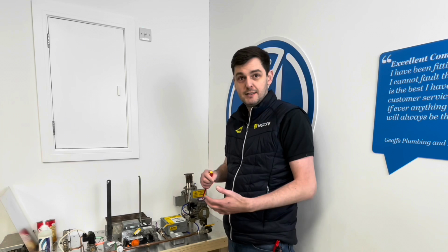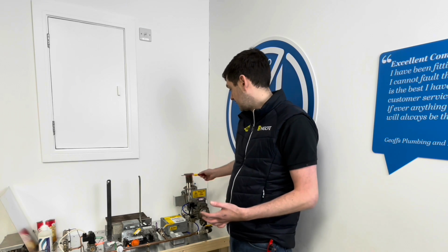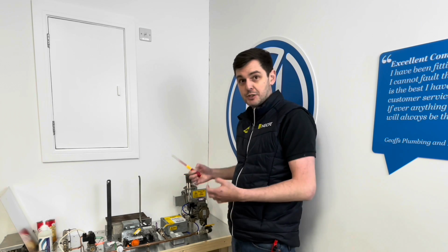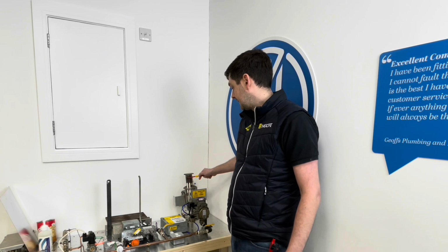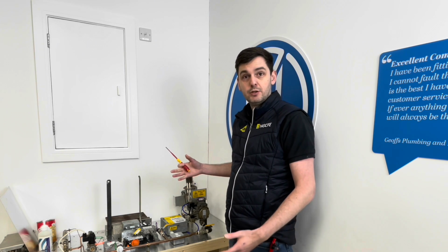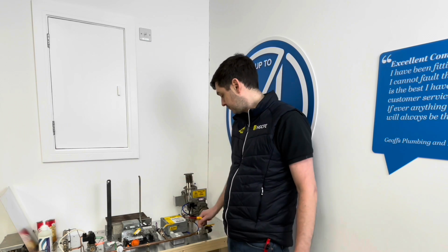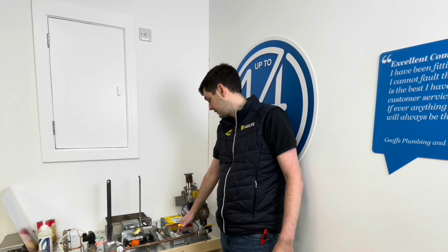Now, this process is instantaneous, and you'll notice that as soon as the flame's established, the ignition probes will stop sparking, because the board's already sensed that there's DC current there instantly, and it'll just stop trying to ignite because it knows there's a flame present. So let's have a look at it in operation.